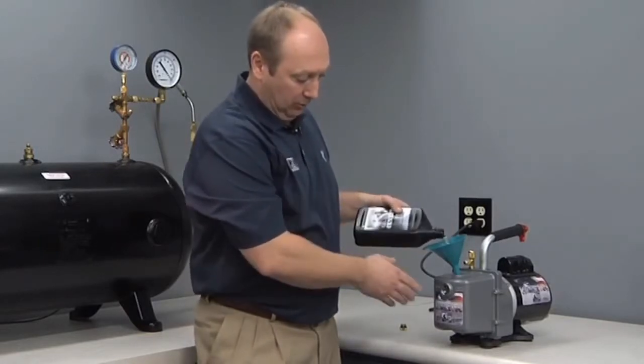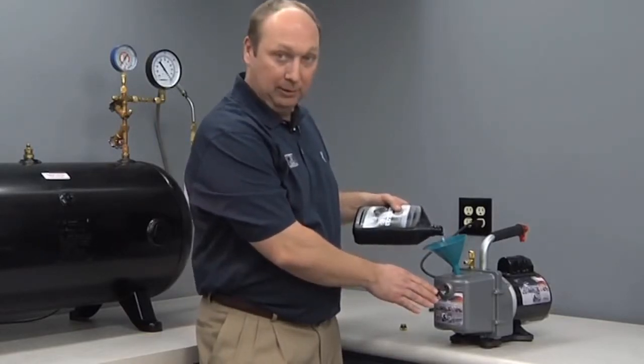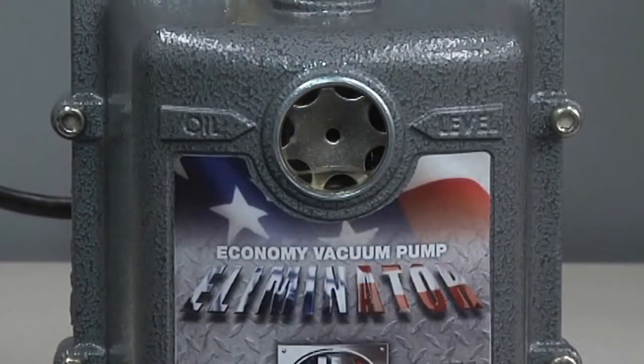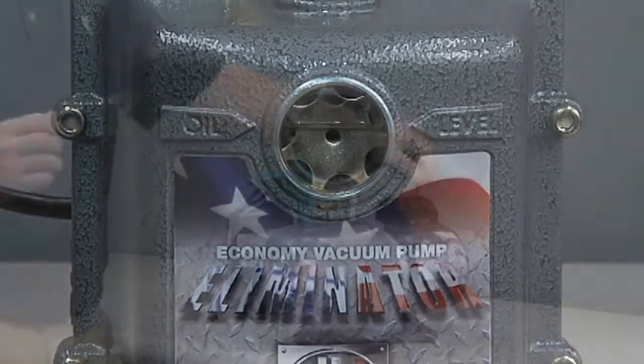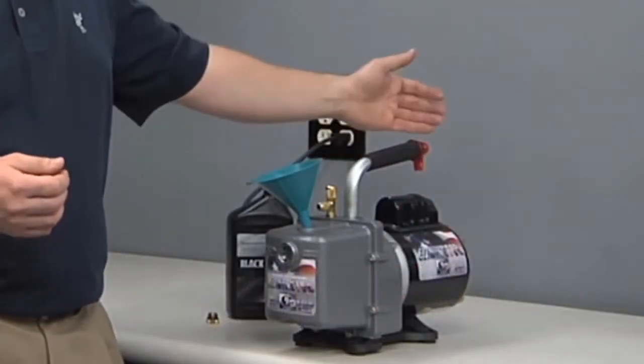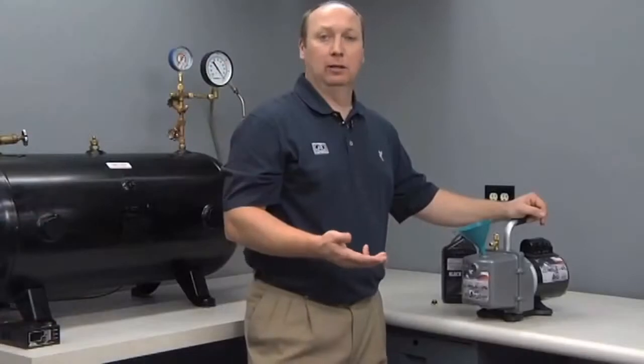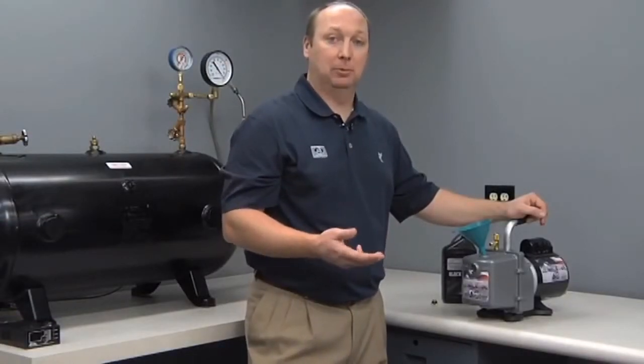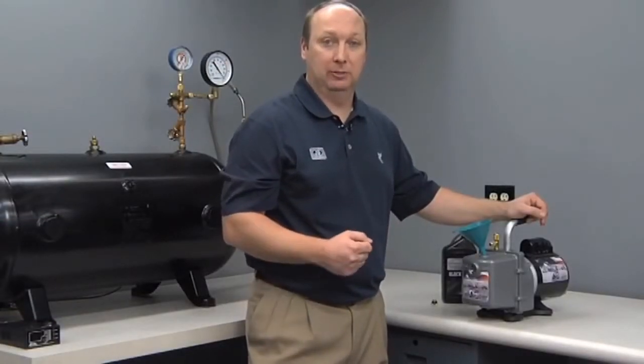It's important to set the oil level properly on the eliminator. On the eliminator pump, we have oil level engraved on arrows. You simply need to ensure that the oil level lines up with the arrows and you will have the maximum amount of oil. If oil is overfilled, it may exhaust out through the handle. If oil level is too low, it won't seal properly and you won't achieve your desired vacuum level.